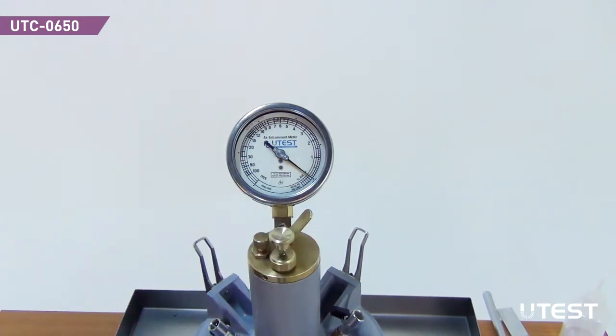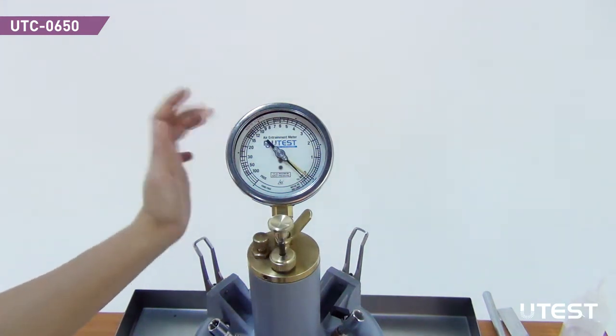Pump air into the air chamber until the gauge hand is on the initial pressure line. Allow a few seconds for the compressed air to cool to normal temperature. Lightly tap the gauge to stabilize.